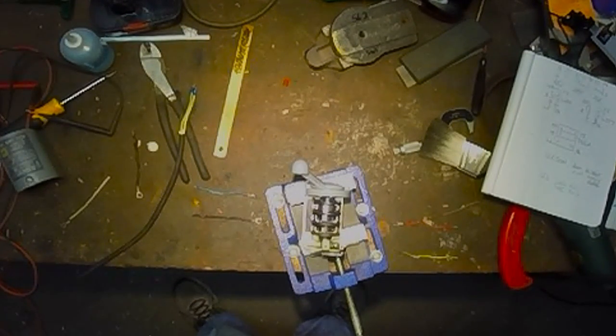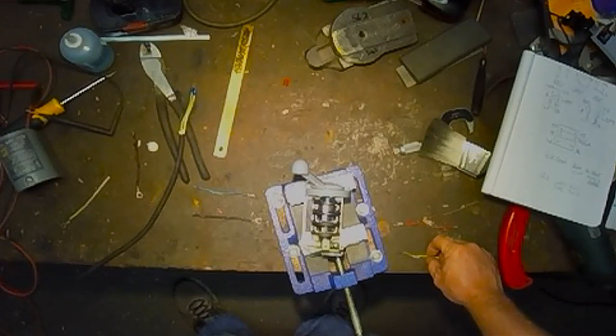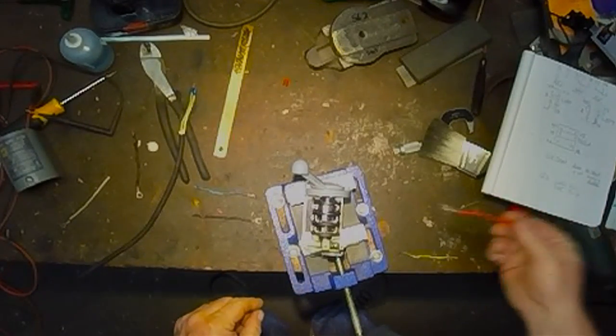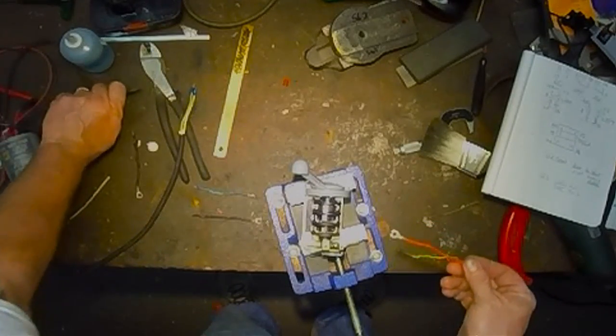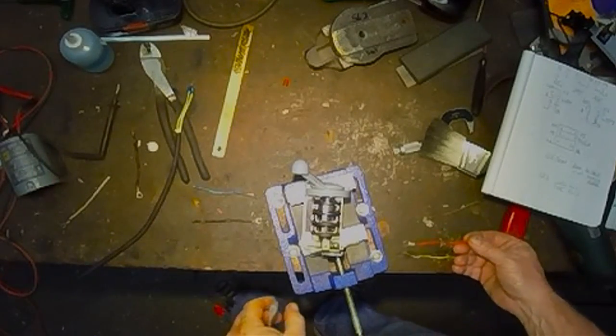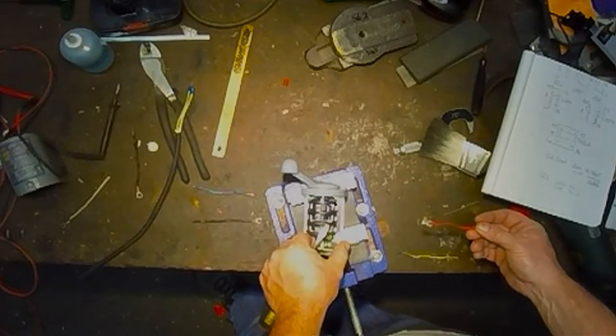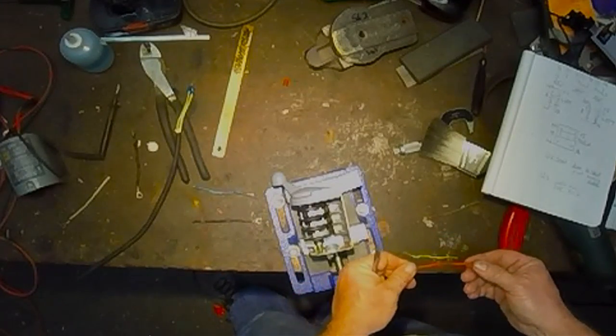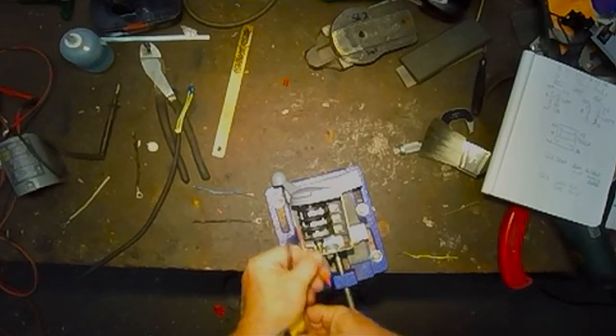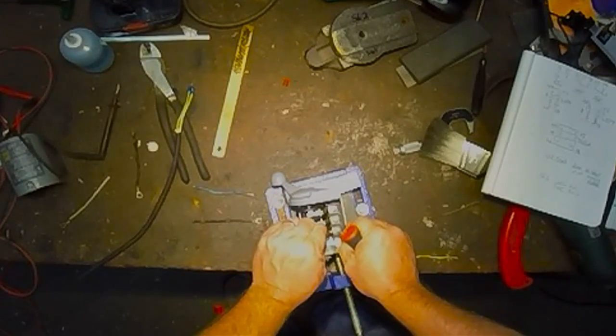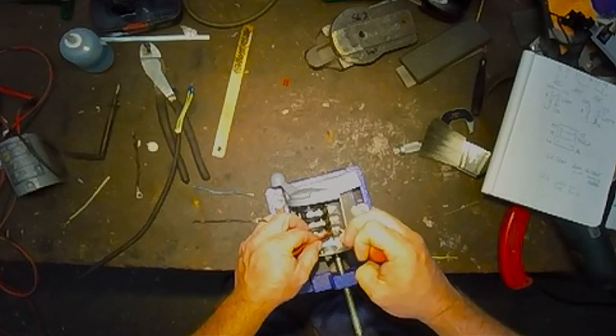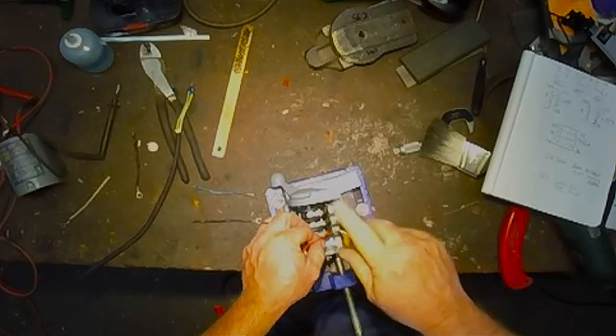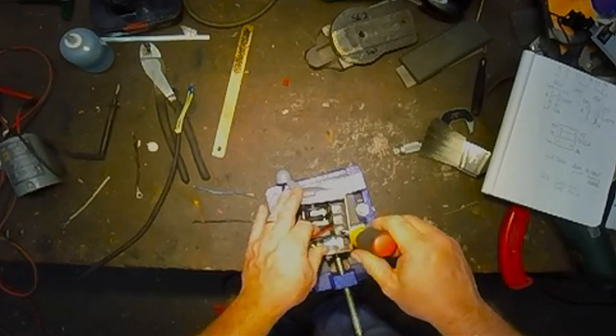Let's just jump right into this for the first connection here. This little red wire is just a representation of what you're going to be using. This one's going to be on number six, P1 from the motor is P1. I like spade connectors on these things, but you can use ring connectors. The spade connectors can slip out if there's a vibration issue. The ring connectors won't ever vibrate out.